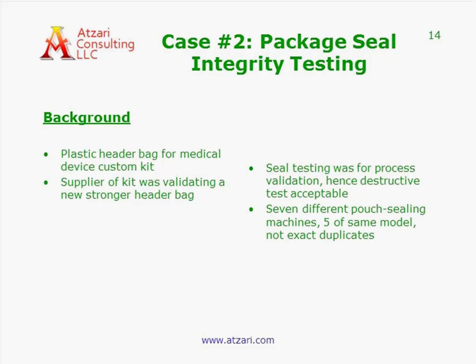They found that with all the handling, the header bag they were using was not as strong as they wanted, so they picked a thicker material and had to validate that new seal. These guys were not experts in process validation, so they hired us. The seal testing was done to validate the seal method. In this case, we could use destructive tests because we were validating the seal — you would have to destroy it to know if it was good, so a destructive test was needed to gain that confidence.